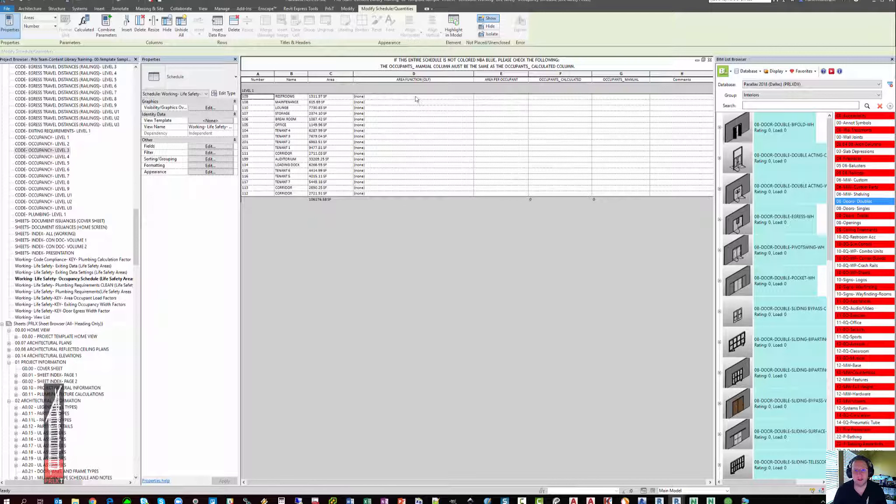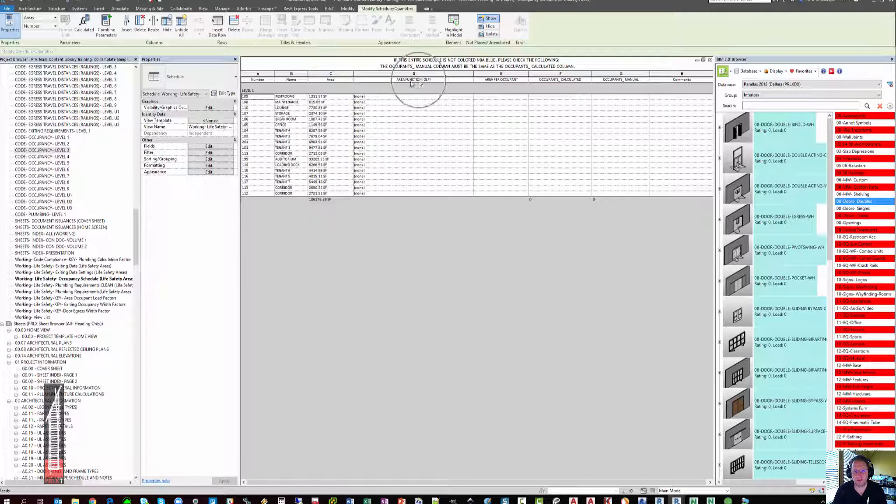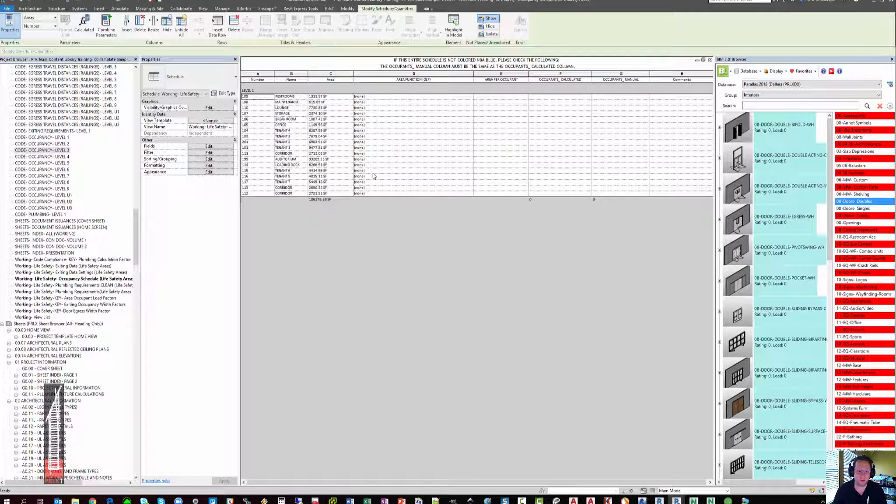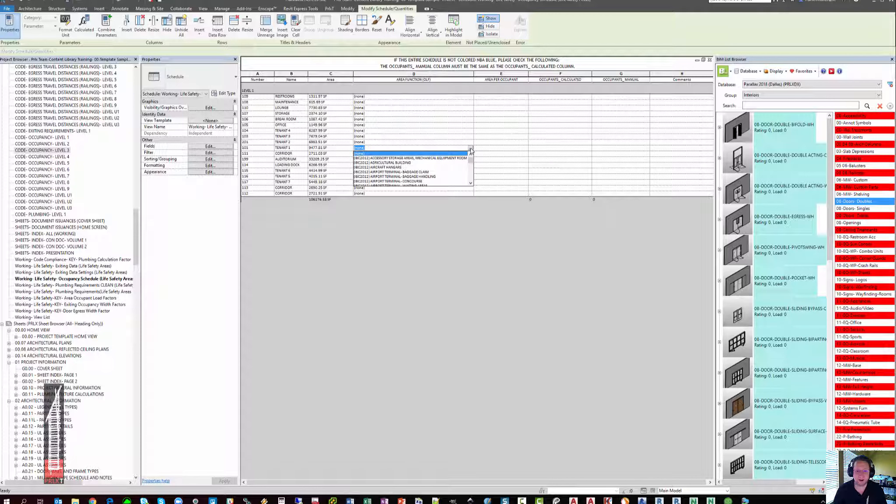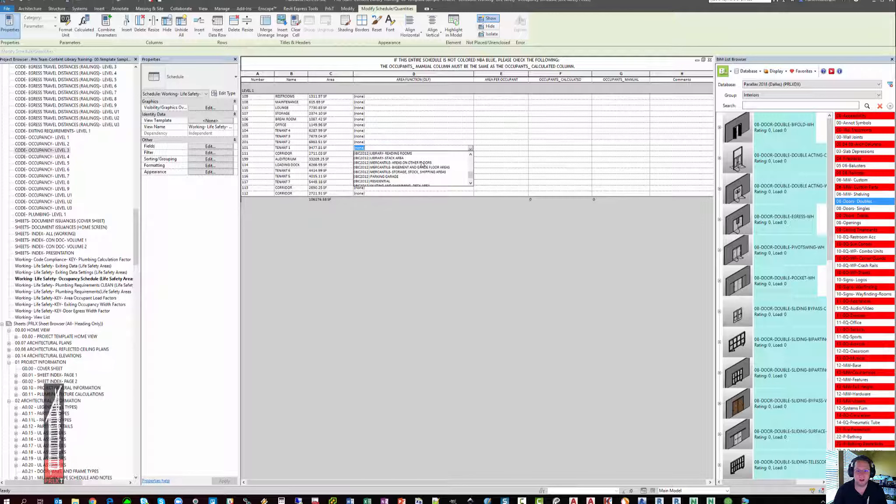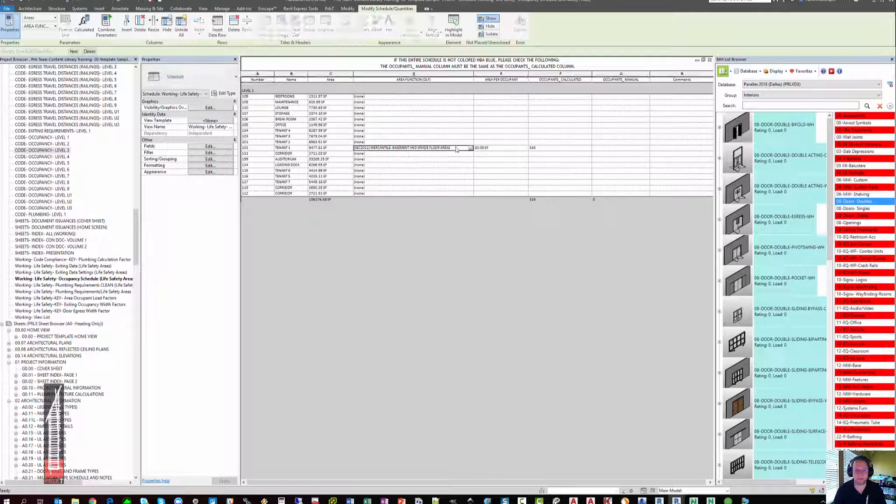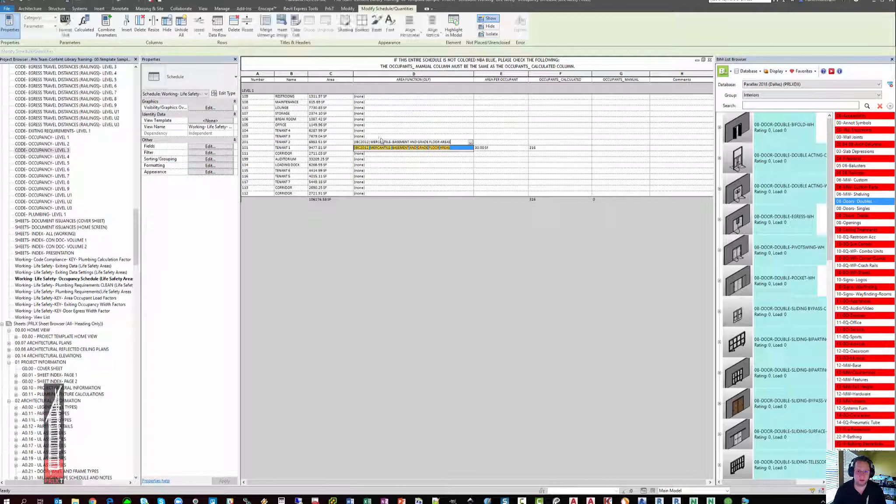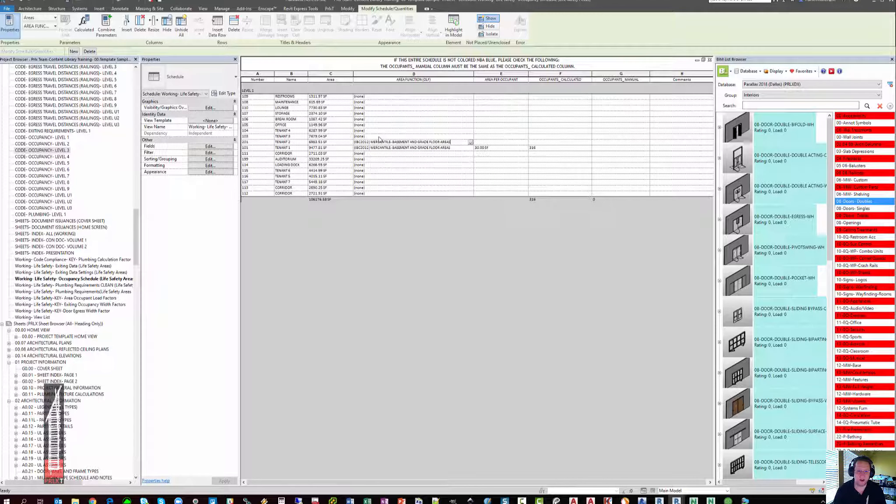First thing that you need to do in this schedule is you need to fill out the area function or the occupant load factor from the IBC code. If you click anywhere that it says none, you'll see that this is actually a dropdown that is populated with the IBC 2012 occupant load factors. For instance, for this tenant space, I'm going to pick mercantile areas on basement and grade floor areas. You can then copy and paste similar occupant load factors anywhere that you need to use them in the schedule.